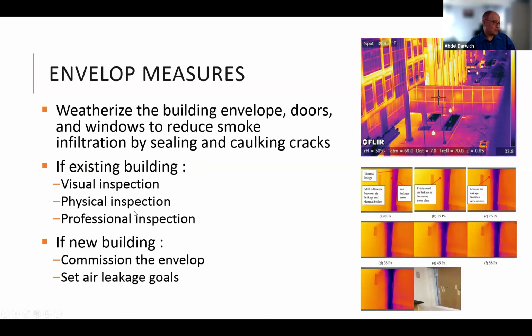You can also take it to the next level, which is what we call infrared imaging, and you can see it here on the right. There is a construction wall at the bottom right, and you would think, oh yeah, that's basically sealed. But when you look at it with an infrared camera and increase the pressure in the building from 0 Pascal to about 60 Pascal, you can see it getting darker and darker in blue, which means there is air passing. So that's a leak that you have to address. If it's a new building, usually we ask you to commission the envelope, so make sure that the envelope is tested before the new building is delivered to the client.